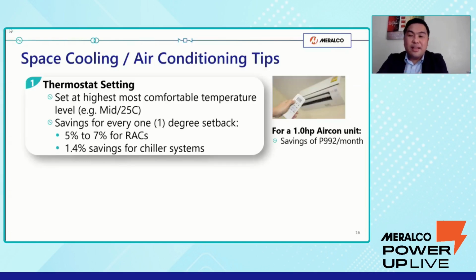So here are some tips on the thermostat settings that you may apply in your facility. First, we must identify, sabi ko nga kanina, yung sweet spot, the highest, most comfortable temperature level, which is ideally at 25 degrees C. Second, as mentioned earlier, there is a 5 to 7% savings for RACs and 1.4% savings for chiller systems per 1 degree setback.